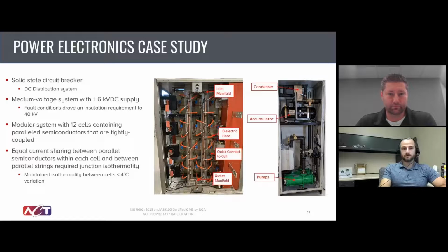There were 12 individual power blocks, 12 individual cells filled with power electronics. Each one of those cells was cooled by a central cold plate. There are modules mounted to both sides of the cold plate and then packaged within a box that had the supporting electronics inside of it. And then 12 of those populated inside of this box to get a really dense package for this DC-DC converter.